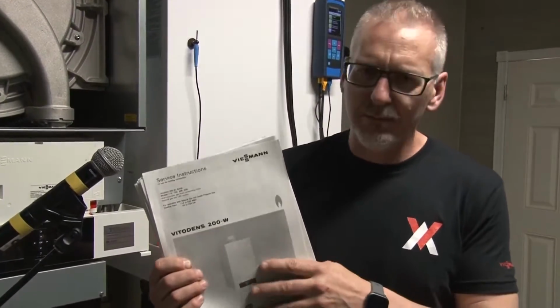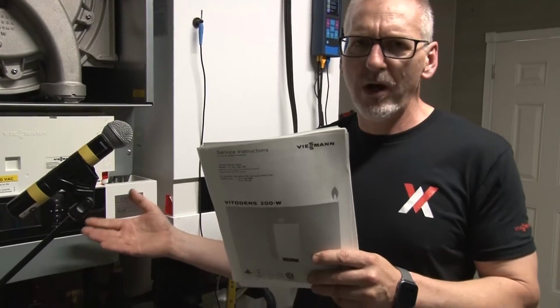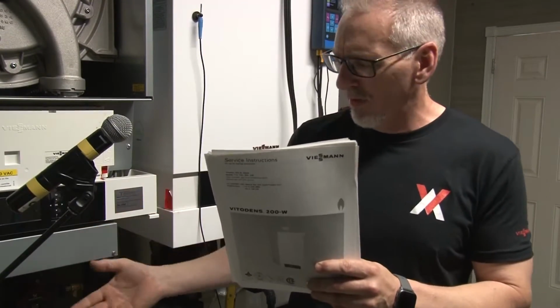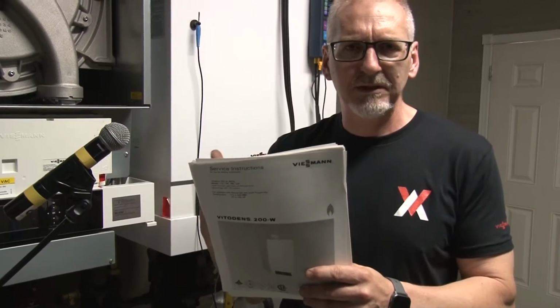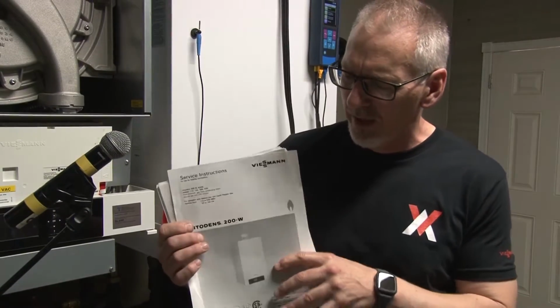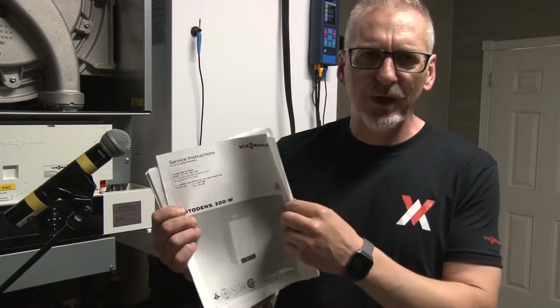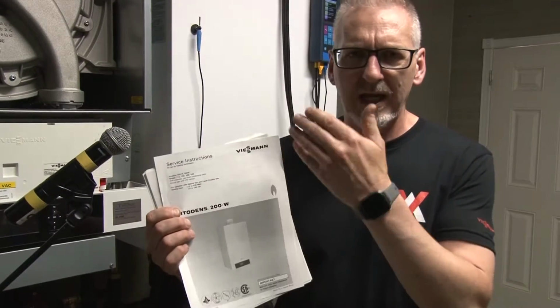What do we want to see in the boiler as far as the quality of that water? And you can't see that by just pouring the water in a bucket and seeing that it's clear. There's a lot of stuff in there that we're concerned about. That information is in the manual here. Any service documentation Viessmann has will give you that information.